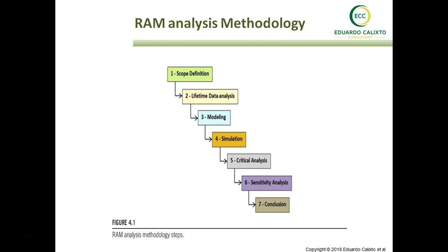Okay, so it's important to consider that, of course, it depends on the time that you are assessing your equipment. Not all the components will fail in this period of time, just as not all the failure modes will happen in this period of time. Mostly, to see all the failure modes and have enough data to model a PDF for failure modes, you need to run the equipment for the whole life cycle. And of course, the most critical equipment will always show up with some failures at component level, in some cases in different failure modes, but not all. We need to be aware of that.